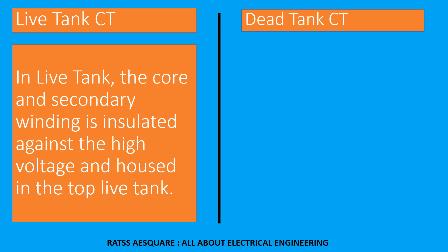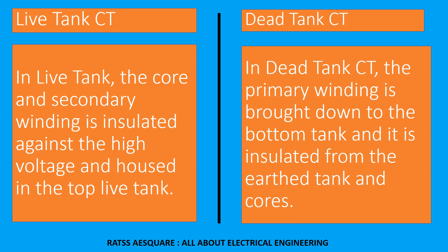In live tank CT, the core and secondary winding is insulated against the high voltage and housed in the top live tank. In dead tank CT, the primary winding is brought down to the bottom tank and it is insulated from the earthed tank and cores.